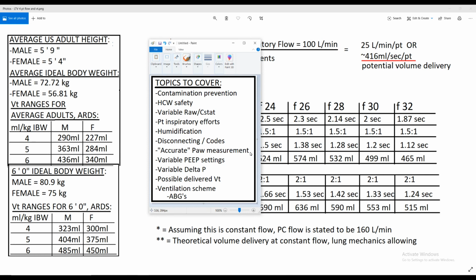The vent is going to have its airway pressure measurement, which is done at the connection that is proximal to the vent. The connection that is proximal to the patient, with that little O2 adapter with a manometer, is where we would get our semi-accurate airway pressure measurement. Variable PEEP settings we said we can do, because each one of these patients can have an individual PEEP set on that external exhalation valve.